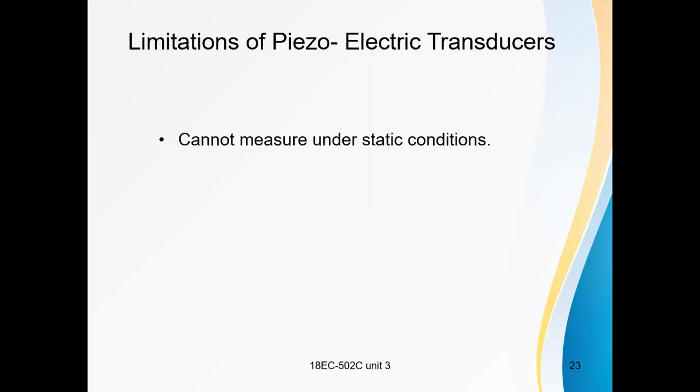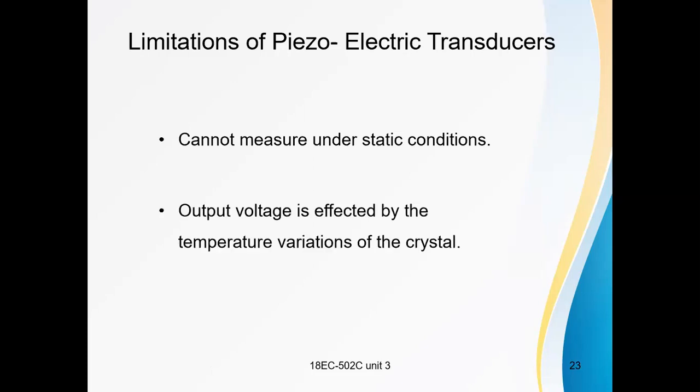There are some limitations. It cannot measure under static conditions. This piezoelectric transducer measures force and pressure, but it cannot measure under static conditions. And the output voltage is affected by the temperature variations of the crystal. These are the limitations.